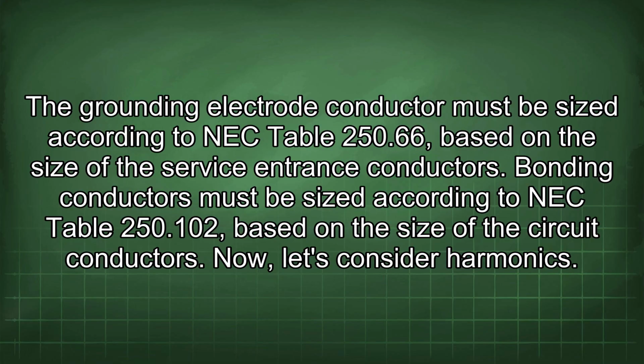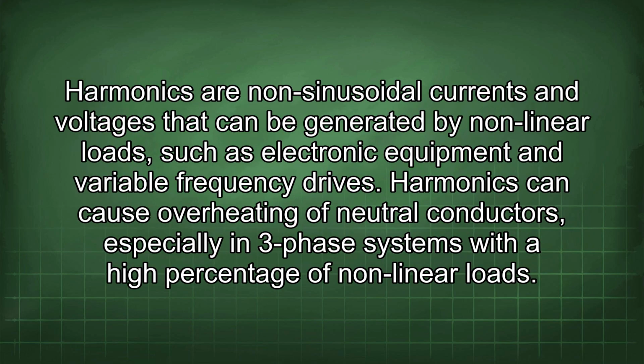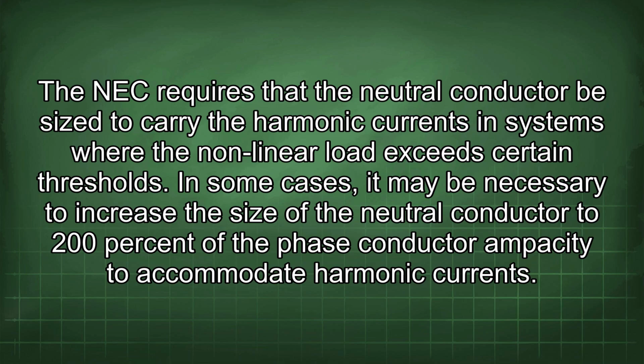Now let's consider harmonics. Harmonics are non-sinusoidal currents and voltages that can be generated by nonlinear loads, such as electronic equipment and variable frequency drives. Harmonics can cause overheating of neutral conductors, especially in three-phase systems with a high percentage of nonlinear loads. The NEC requires that the neutral conductor be sized to carry the harmonic currents in systems where the nonlinear load exceeds certain thresholds. In some cases, it may be necessary to increase the size of the neutral conductor to 200% of the phase conductor ampacity to accommodate harmonic currents.